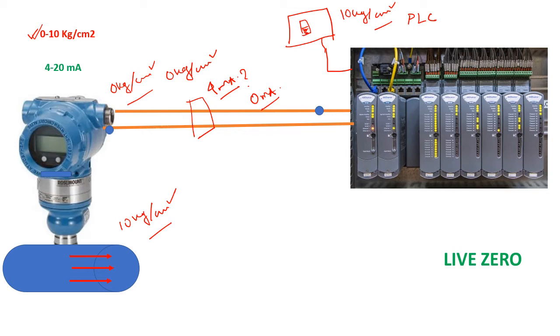When a terminal becomes loose or the wire gets broken, the signal transmitted to the PLC becomes 0 milliamps. So whether the process variable is actually 0, or there is a cut wire, or there is any problem with the transmitter, we could not diagnose if we kept the transmitter range from 0 to 20 milliamps. This is the reason why 4 milliamps has been used.